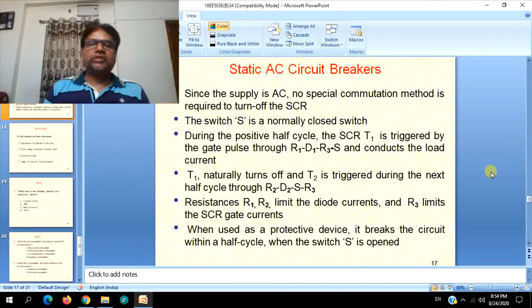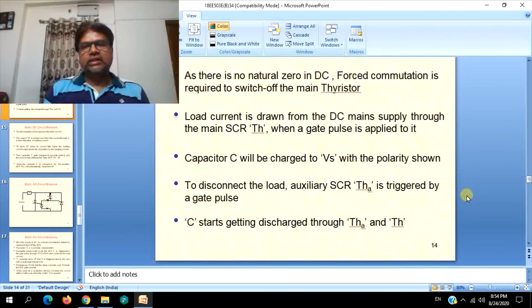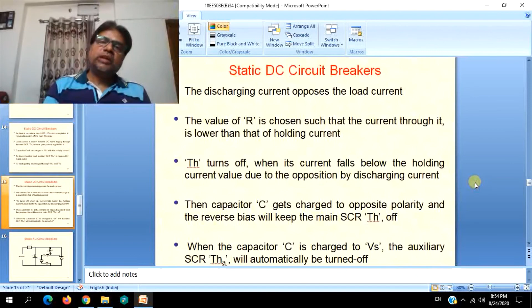When used as a protective device, it breaks the circuit within a half cycle. That is the most important feature when compared to other conventional electrical circuit breakers. Half cycle means it is 10 milliseconds, not 5 seconds. Within 5 milliseconds of time, the circuit breaker trips or breaks the circuit. That is how static AC circuit breakers and static DC circuit breakers work, and that is the concept of static circuit breakers, which eliminates all the long breaking times.